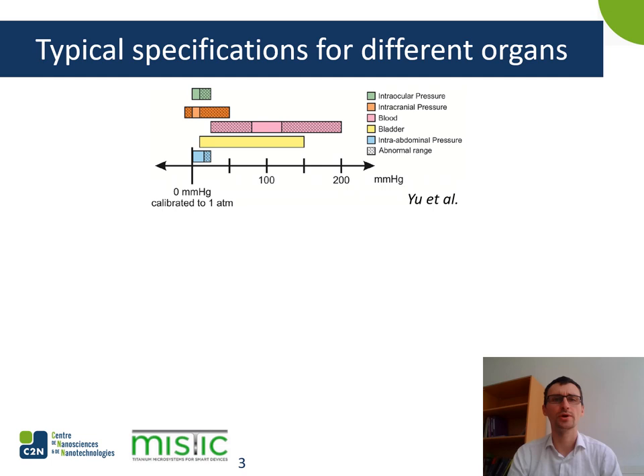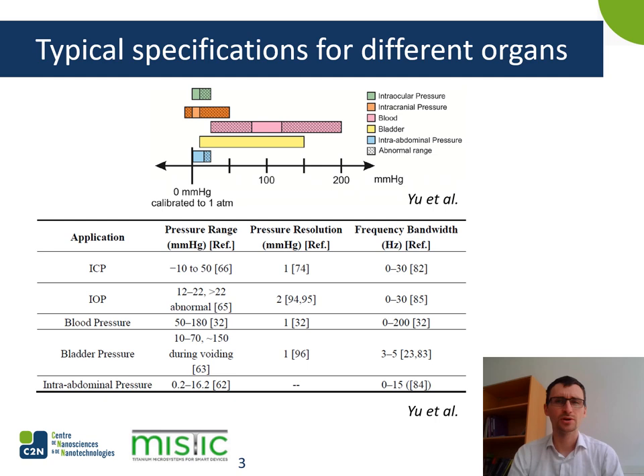Let's now have a look at the specifications we need to reach to create such sensors. Here we have the ranges of pressures for different organs and fluids — both normal and abnormal ranges. We are working at very low pressures compared to other applications such as sensors for the aircraft industry. The pressure within the eye is completely different from that in the heart. We can go from minus 10 to 50 mmHg for intracranial pressure and from 50 to 180 mmHg for blood pressure. We want a sensor which can address all these ranges, with a minimal resolution of 1 mmHg, which would be enough for every application.